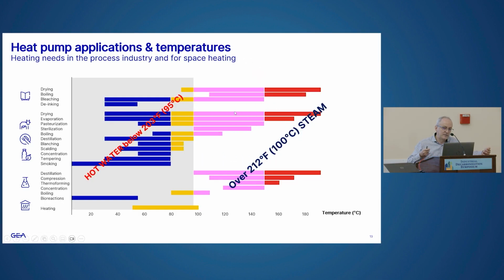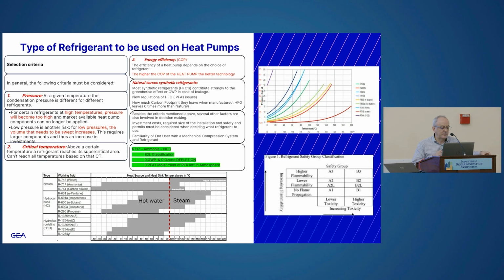If you want to go over to the steam line, higher temperatures, it has to be with a different technology, or in the heat pump using compressors it has to be with a different refrigerant. So that makes a choice of refrigerants. Some refrigerants are going to be based on your critical point, the critical temperature of that refrigerant. So basically, that defines the heat pump, and it's going to define the heat pump cost, the heat pump technology, and the heat pump COP. The higher the pressure of that refrigerant, the higher the cost of the heat pump because you're running with components rated at high pressure. The lower the pressure of that refrigerant, it's probably going to be a lower cost heat pump, but at the same time, you're sacrificing COP. So you have to find that break point, which one you want to choose.